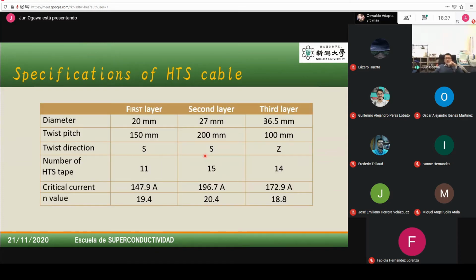This table shows the specification of the HTS cable. We use multifilamentary non-twist bismuth tapes. The critical current is 180 amps, thickness is 0.3 millimeter, and width is 4.3 millimeter.